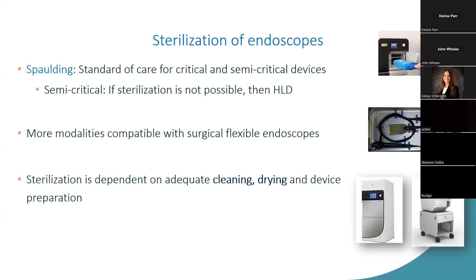Some key points when it comes to sterilization for flexible scopes. Remember, surgical scopes, many are compatible with vaporized hydrogen peroxide systems. You'll find STERRAD compatibility within the IFUs for Olympus. vPro often is not in the IFU, but it's in customer letters. ETO, again, compatible with all Olympus scopes.